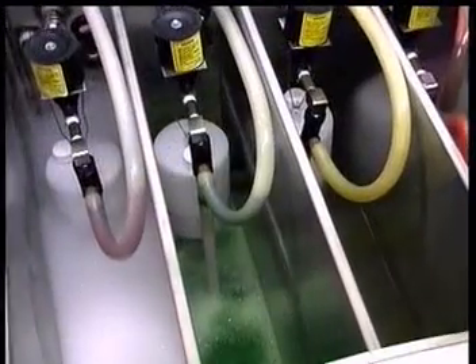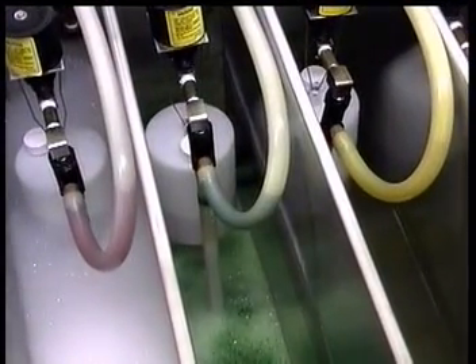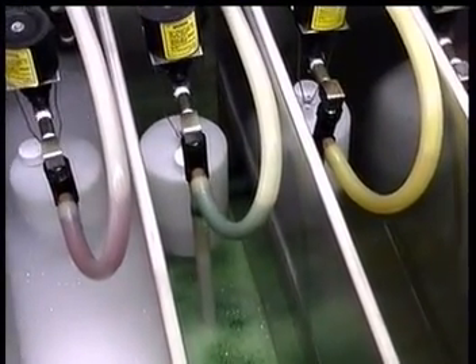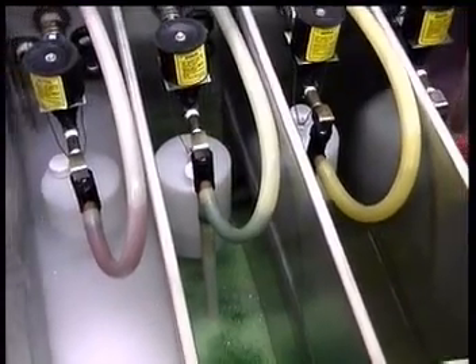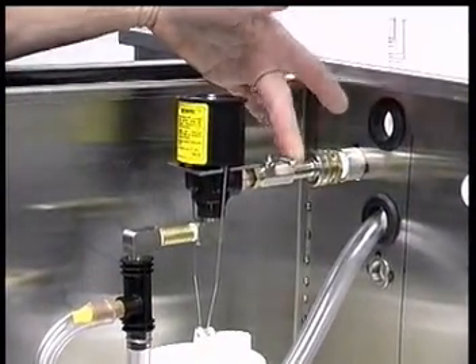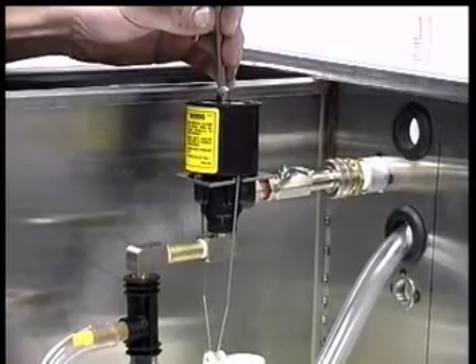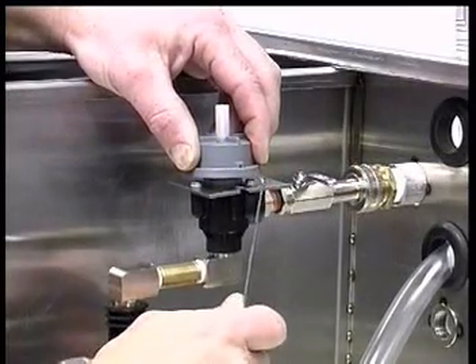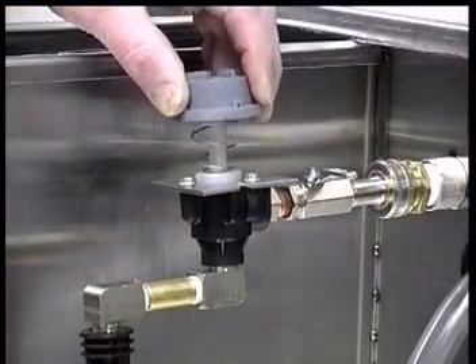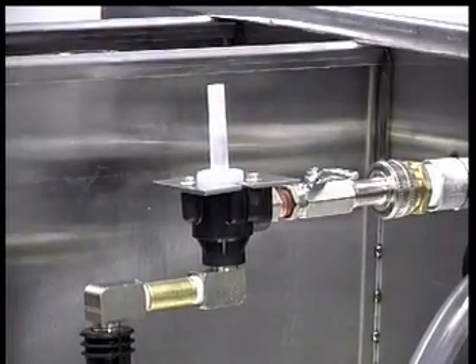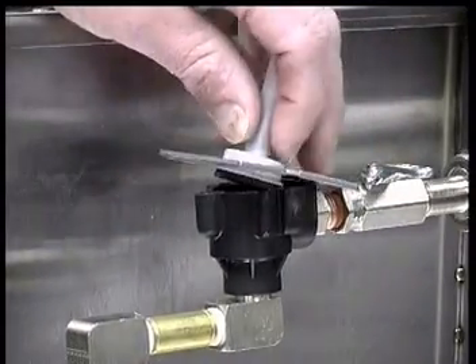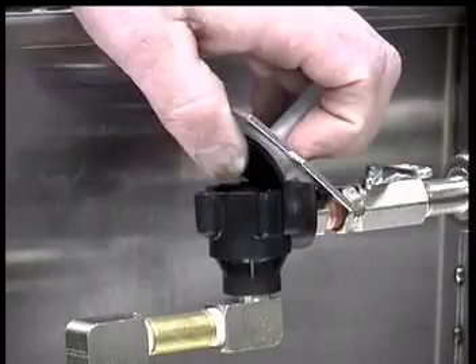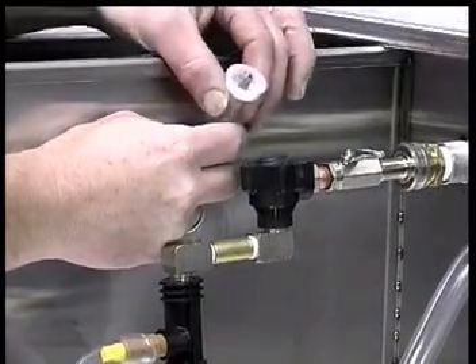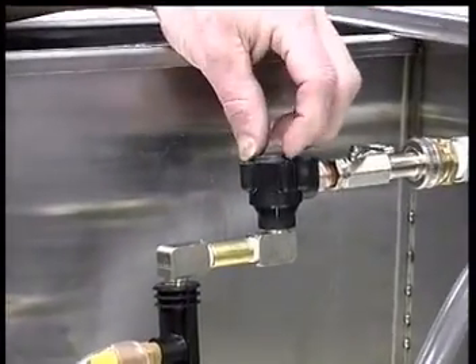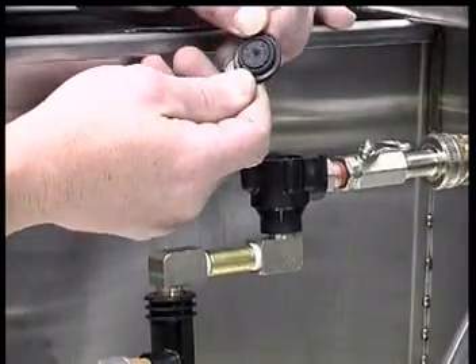If the Hydrominder in either the water tank or the chemical mixing tank is stuck open or will not open when called for, the first step in repair is to close the quarter-turn valve and remove the black plastic switch cover. Then remove the float bail and the magnet and spring. Expose the diaphragm by removing the top portion of the valve body. Check for debris or a badly worn diaphragm. If the diaphragm is bad, replace it and reassemble the valve body in the opposite order.